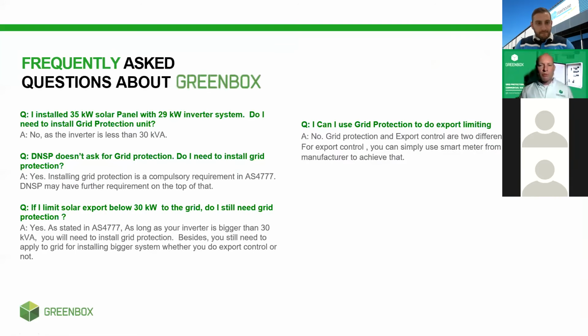We'll run through some basic questions, and I've done a few already. So, I've installed 35 kilowatts of solar panels with a 29 kilowatt inverter. Do I need to install a grid protection unit? No, the DNSP doesn't ask for grid protection. Do I need to install grid protection? Again, yes, as soon as you get over the 30 kilowatt, you have to install it. It's a compulsory thing according to AS 4777, no matter what the DNSP tells you.